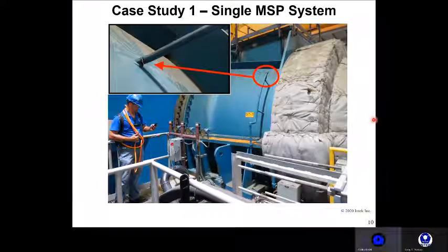The leak that was found and temporarily patched was on the hood spray pipe seen here. This happened to be a high vibration area, and several of the other units had started to show cracking on these hood sprays. This plant has 4 identical units, and the action taken was to replace this connection with a flex line. This leak accounted for 30 of the 50 total SCFM.